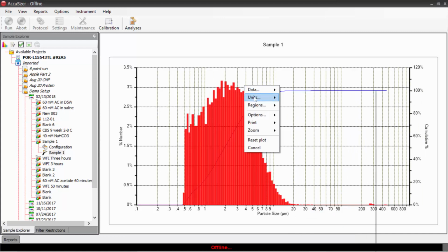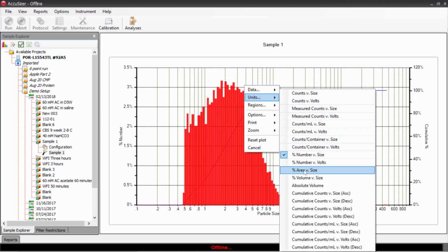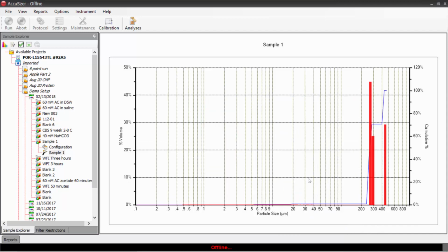Maybe I'm interested in seeing what the volume distribution would look like. I could come down over here to volume versus size. And now I'm saying that looks a bit odd. All of the volume seems to be out at a few particles out here at the right-hand side. And a few large particles could greatly shift the appearance and the calculations in this result.